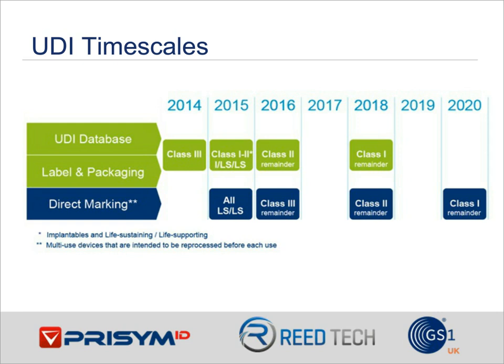There's not a lot to add apart from Gary's comments. Companies who are planning their journey on UDI should really start looking at creating the product codes. That's the DI element, assigning what we call GTINs to their product, determining the labeling requirements, understanding the printing and marking technologies they may be using to mark those products, and determining the information that is required for the production identification. So that's the PI, the dynamic information. All of this takes considerable time and resource. So I can only just echo what Gary said. Don't delay.